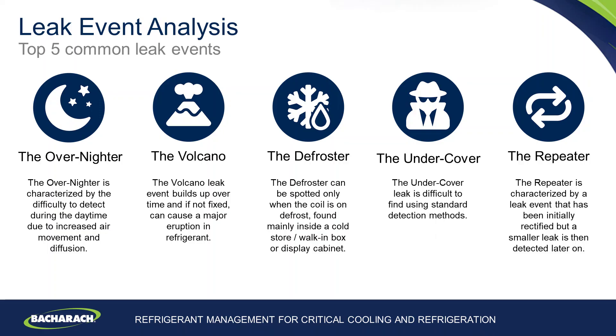So what are the top five common leak events? The overnighter is typically characterised by a difficult-to-detect leak during the day that builds up overnight due to a lack of airflow. The volcano is a leak that starts off small, that can continue for a period of time, and if not fixed early, will erupt into a large refrigerant emission. The defroster is a leak that comes and goes on a predetermined time, spotted only when the coil is on a defrost, usually found inside a walk-in cooler, box, or refrigerated display case. The undercover is a difficult-to-find leak that needs time and dedication by the engineer. The repeater is characterised by a leak event that has been initially rectified, but once rectified, a smaller leak is then detected later on.